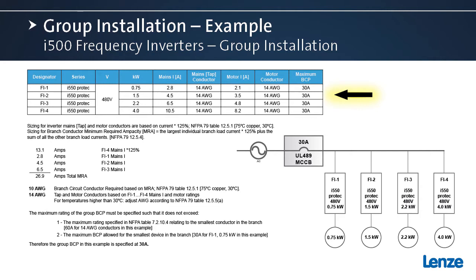in this group. In this example, there's 4 i500 series ProTech inverters. They're all 480 volt. 4 different power sizes, 0.75 kilowatt, 1.5 kilowatt, 2.2 kilowatt, and 4 kilowatt. And we list the mains current, the motor current, and the maximum branch circuit protective device allowable for use with these frequency inverters. To start the sizing, we'll look at the tap conductors first.